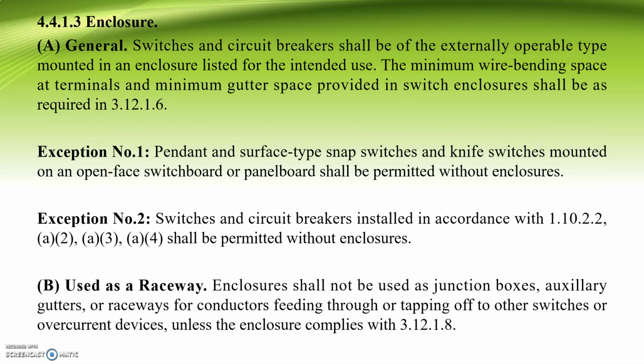So chapter 4.1.3, in general, switches and circuit breakers shall be of the externally operable type mounted in an enclosure listed for the intended use. So the minimum wire bending space at terminals and minimum gutter space provided in switch enclosures shall be as required in chapter 3.12.1.6. So exception number 1. Pendant and surface type snap switches and knife switches mounted on an open face switchboard or panelboard shall be permitted without enclosures. So exception number 2. Switches and circuit breakers installed in accordance with chapter 1.10.2.2, A2, A3, and A4 shall be permitted without enclosures.